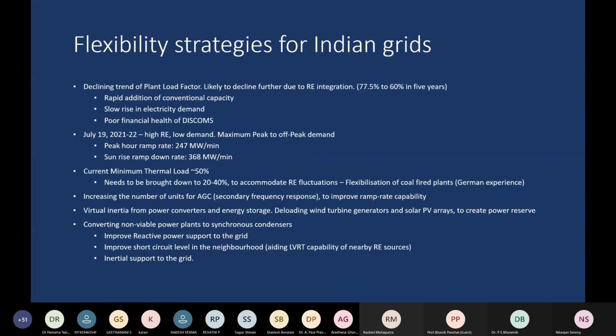Currently, in our thermal power plants, the minimum thermal load at which the plants can operate is roughly about 50%. What happens if you bring it lower than 50%? There is a problem of flame. The flame stability in the boiler is lost. So the flame goes off, number one. Number two, your main boiler feed pump starts to vibrate at such low rates of water. So this 50% number, the MTL, the minimum thermal load, must be brought down to about 20 to 40%.